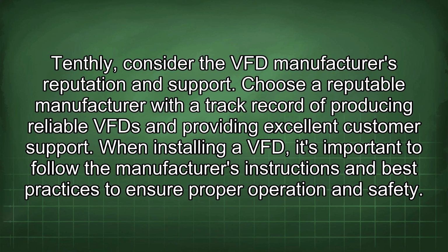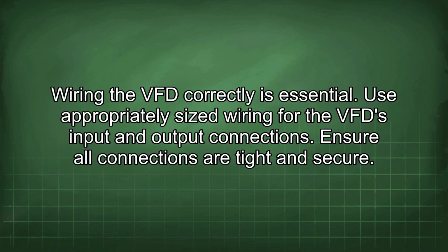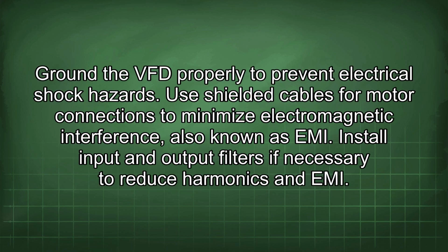When installing a VFD, it's important to follow the manufacturer's instructions and best practices to ensure proper operation and safety. Wiring the VFD correctly is essential. Use appropriately sized wiring for the VFD input and output connections. Ensure all connections are tight and secure. Ground the VFD properly to prevent electrical shock hazards. Use shielded cables for motor connections to minimize electromagnetic interference, also known as EMI. Install input and output filters if necessary to reduce harmonics and EMI.